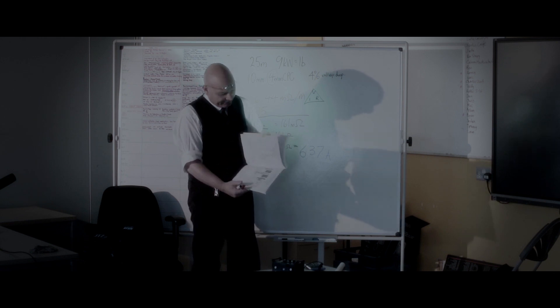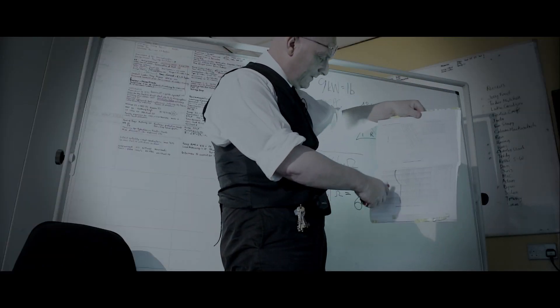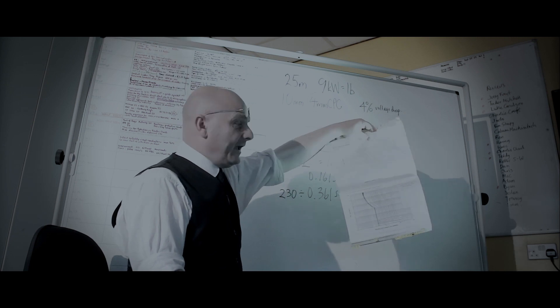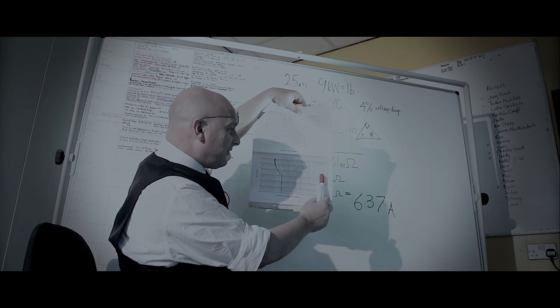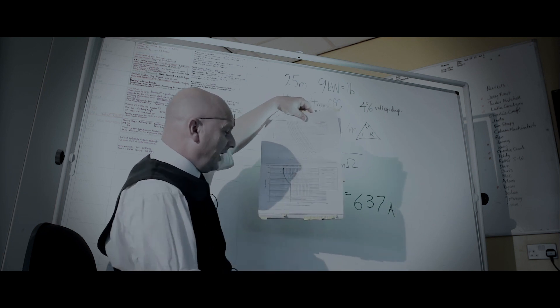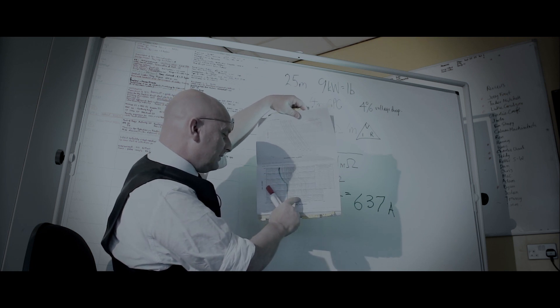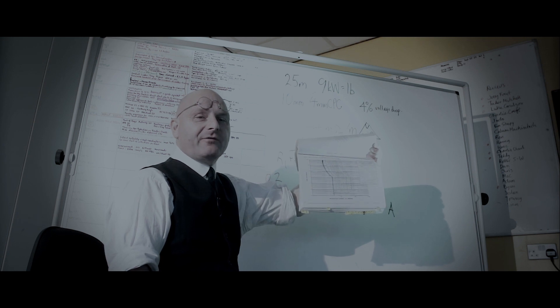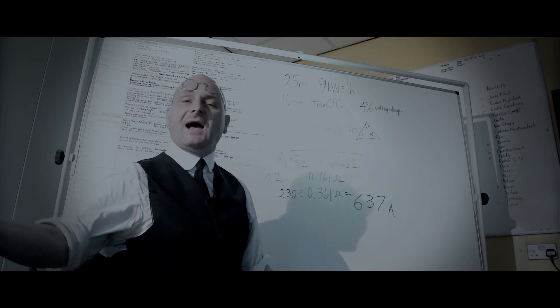I can tell straight away that 637 amps, from the time-current curves which we can find here in figure 3A4, means that an overcurrent protective device of a B40 will disconnect between 0.1 seconds and 5 seconds given 200 amps. If we look at the 40 amp curve and take it down on the logarithmic scale to 600 amps, we're already off the scale. The electromagnetic mechanism in the overcurrent protective device has instantaneously disconnected the supply. So we take time in the adiabatic equation as 0.1 seconds.